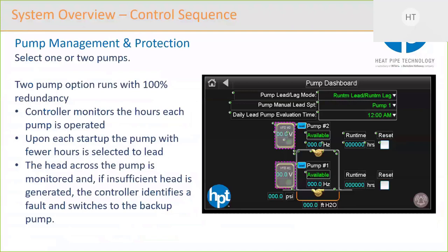So in terms of pump management, I mentioned that we normally have two pumps. The controller will manage those two pumps, and it will count the accumulated hours that each one has run. Every time the system starts up, it'll look at the runtime hours and pick the pump with the lower runtime hours. That is to balance out the loading on the pumps over time. The pumps are 100% redundant, so you only need one pump to run the whole system. If that pump were to fail, the system would detect that and start running the second pump.